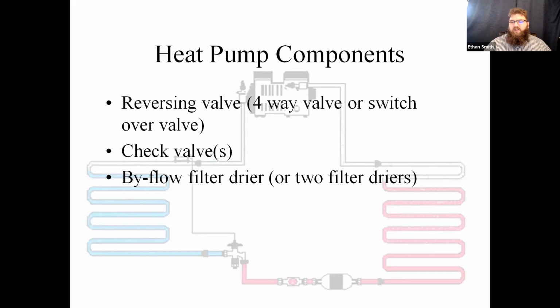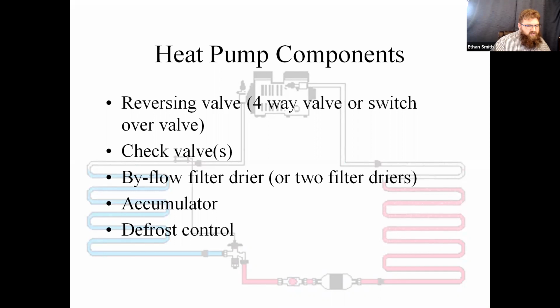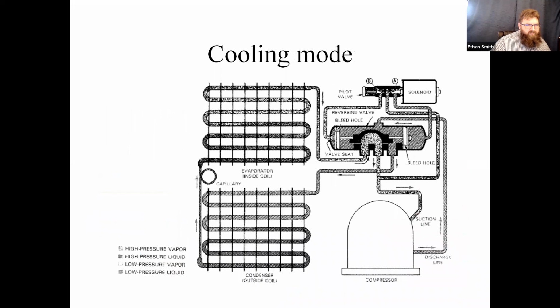Biflow filter dryers. Biflow filter dryers are a little newer. Prior to that, we would have two different filter dryers that were directional, one in each direction, that had check valves built into them. We also need an accumulator usually to take care of extra refrigerant. So that's going to make a big difference there, having that accumulator. We're also going to have some kind of defrost control. So there's a refrigerant diagram of just a basic unit. We can see some of those features. Mostly this is the reversing valve that I want to talk about. And let's talk about reversing valves.